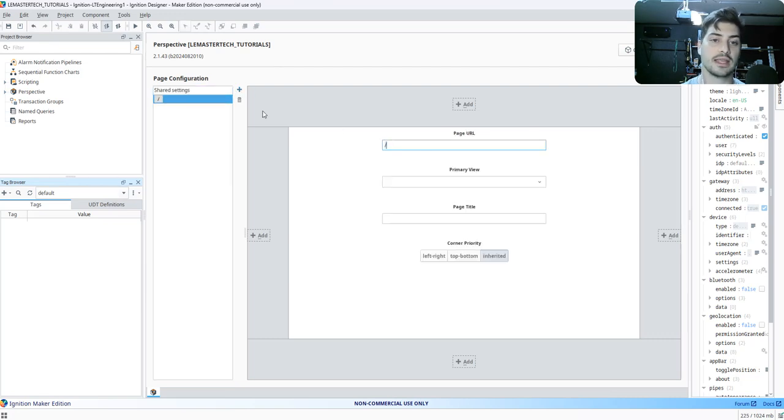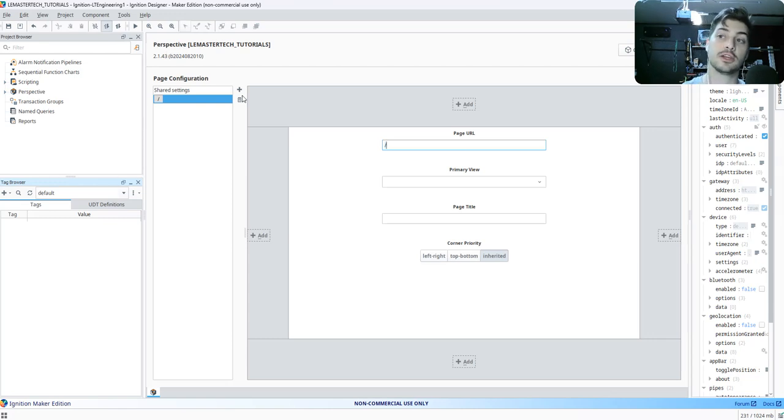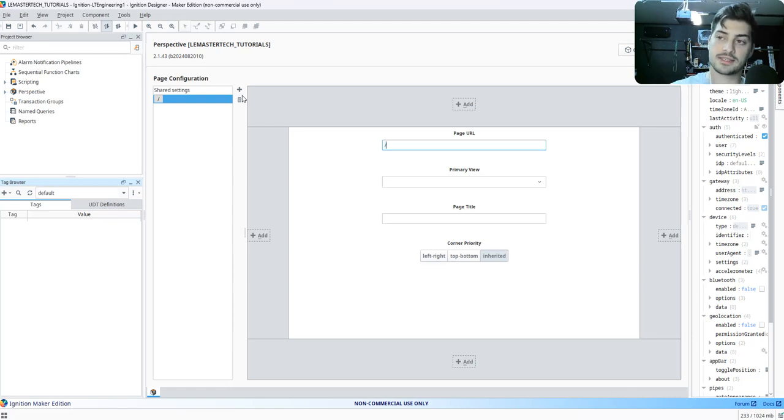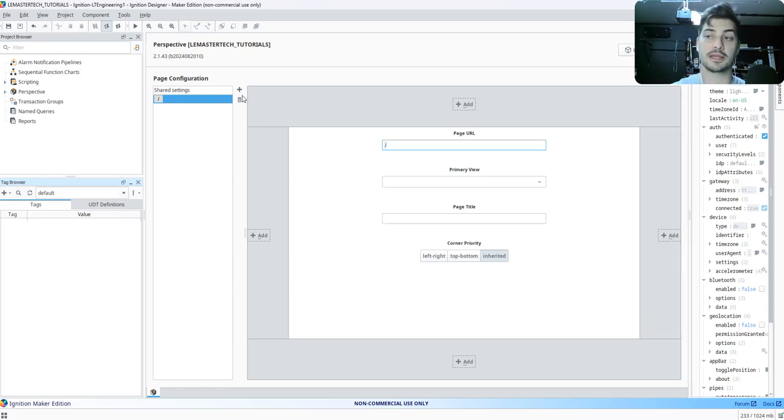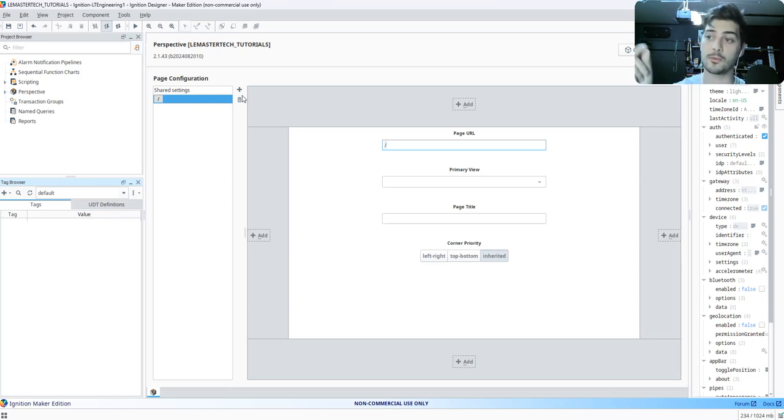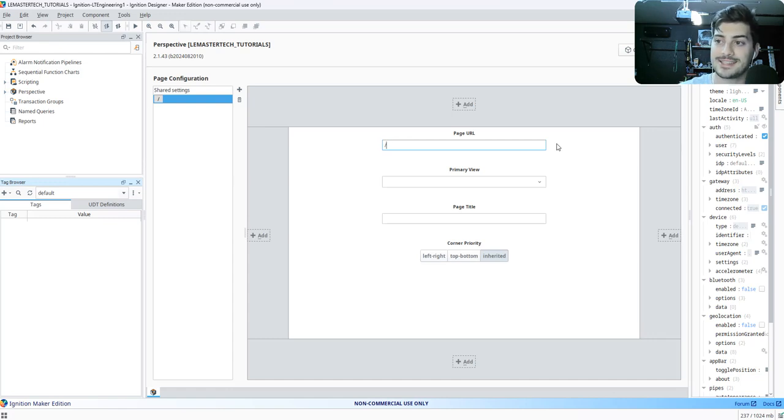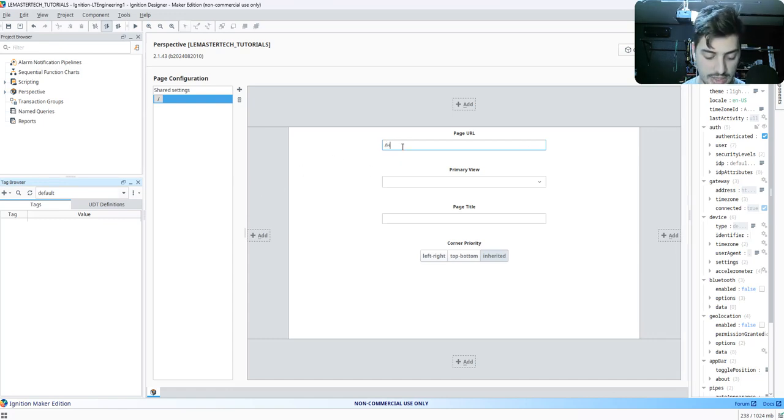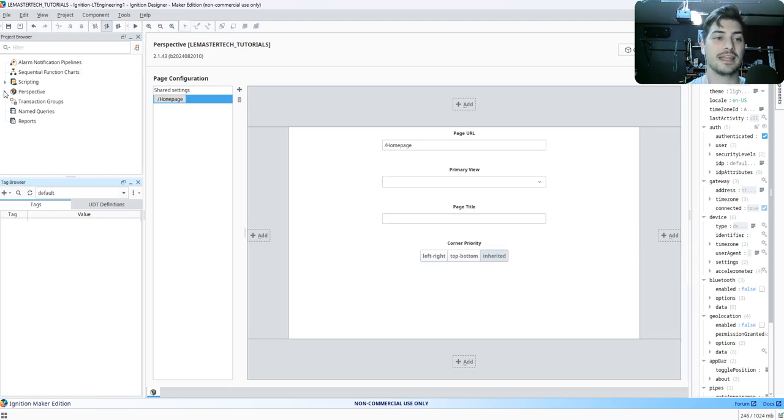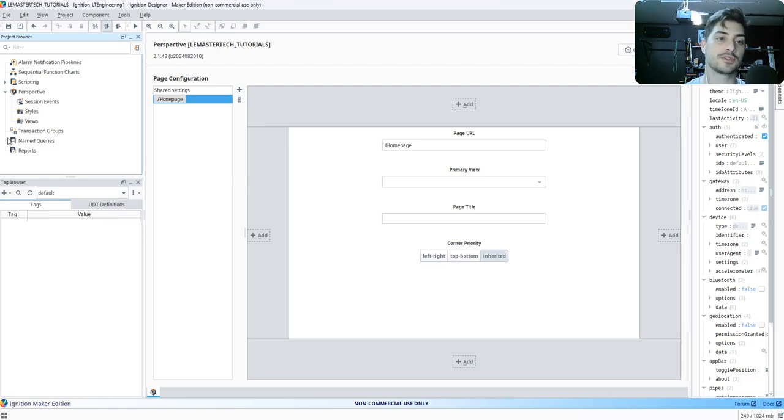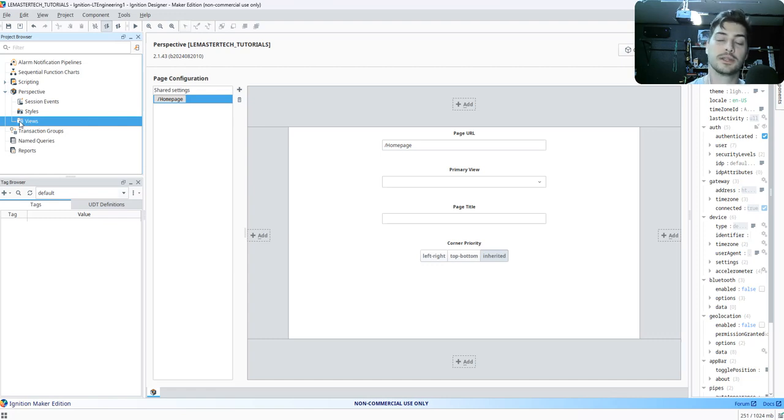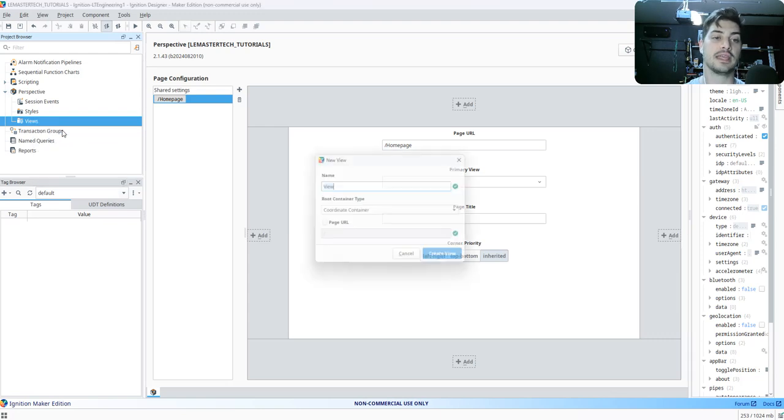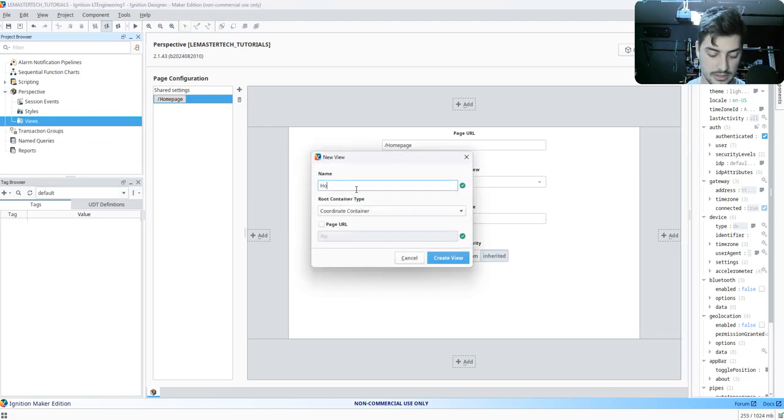And now let's take a look at making a first view. Okay, so let's go ahead and hit the plus on this first view that pops up. We are in Perspective. So again, I talked a little bit earlier, Ignition has two HMI tools: one is called Vision, and it's a conventional, based-on-a-computer software. The other one is Perspective. And it looks to me like Perspective is the only one that's included with the Maker Edition, which is totally fine. But the cool thing about Perspective is it's web-based. And so that means that you can give URLs to every page. So let's just make one and we'll call it slash homepage. And it asks you what primary view you want. But because we haven't created any views yet, there's no views. So we'll expand in the project browser, we'll expand the Perspective section, and you'll see there's an area for views. But it's just an empty folder right now. If you right-click, then you can hit New View, and we'll call it homepage.